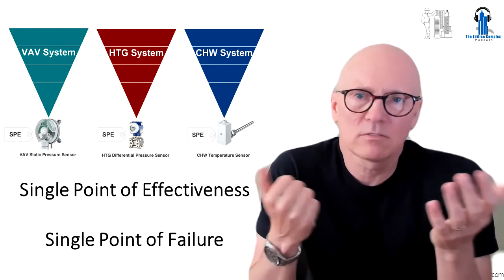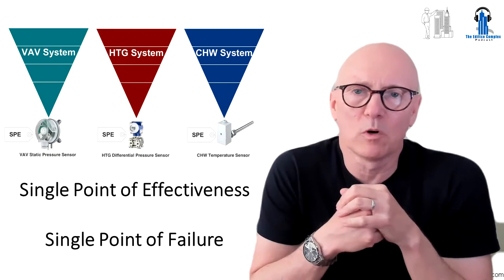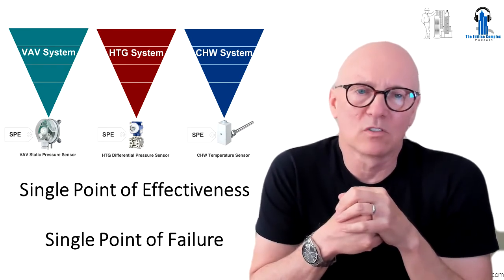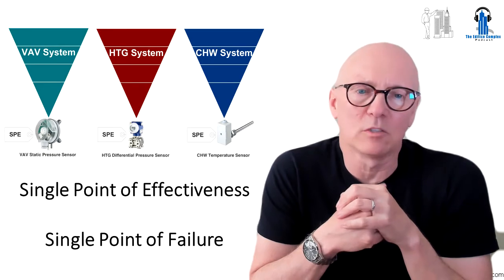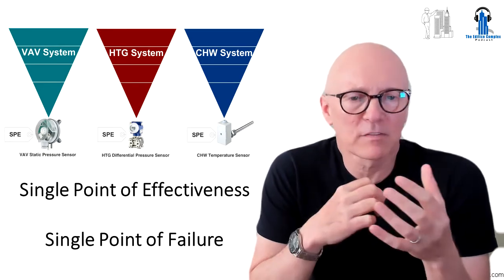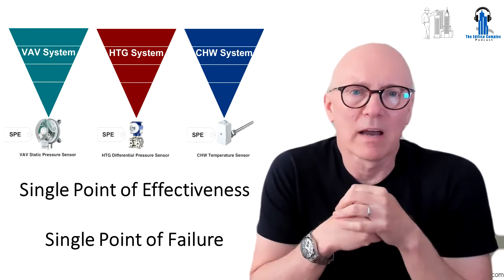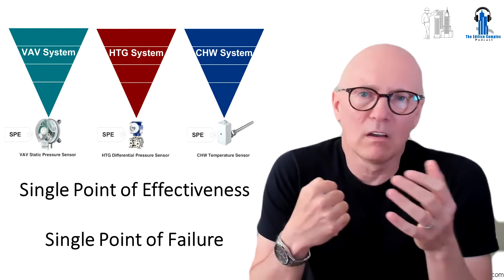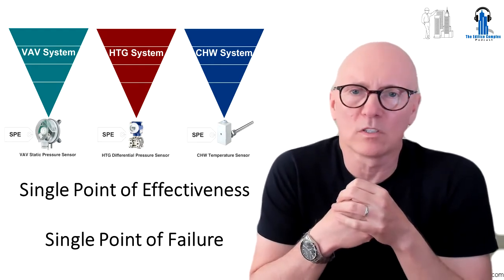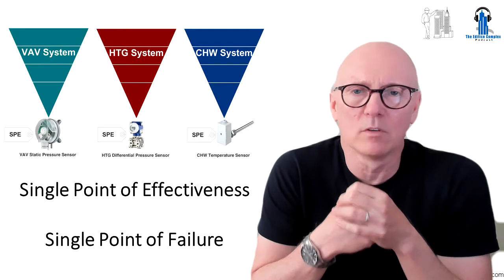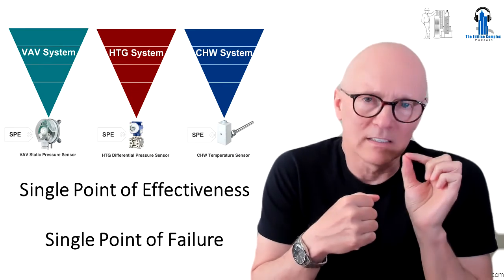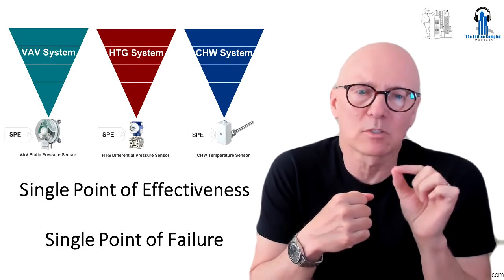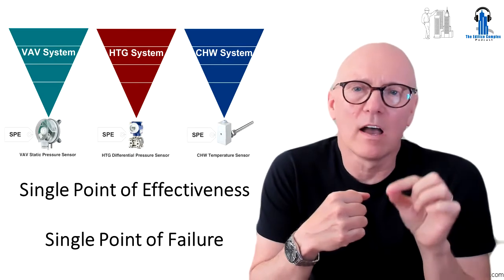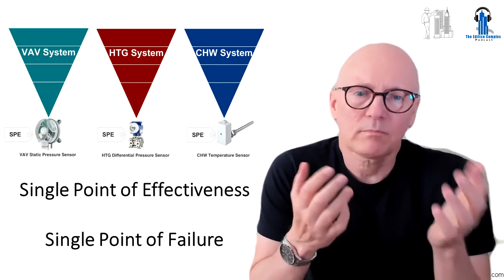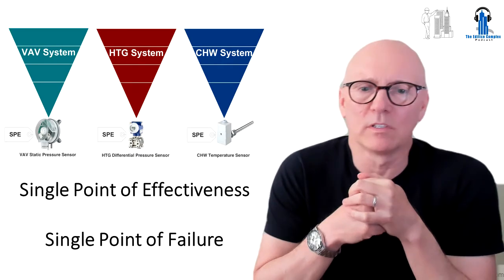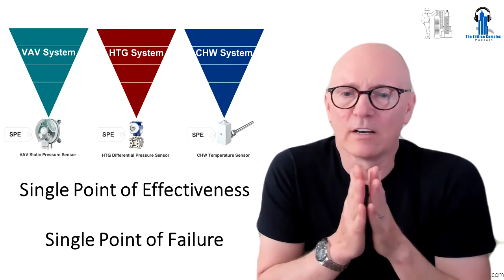And if that thing fails, then the system's not going to be working at all as designed, and certainly not as the predicted energy model. So from an effectiveness and a failure point, that matters. And it's the same with a variable volume hydronic heating or cooling system as well. They all come down to a differential pressure sensor and a distribution pipework that needs to be set absolutely correctly via empirical testing. Complexity is a reality in building design and in construction and in operation.